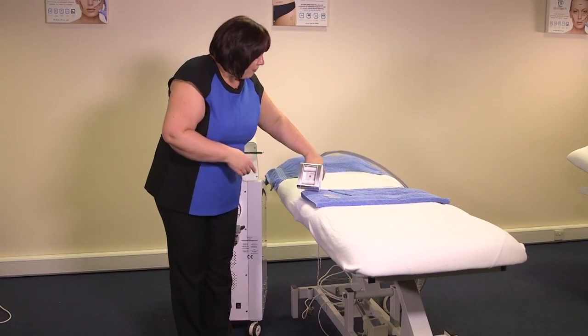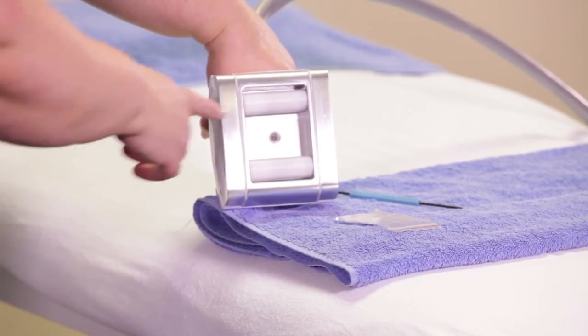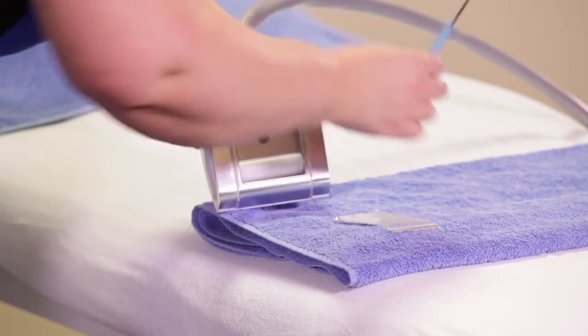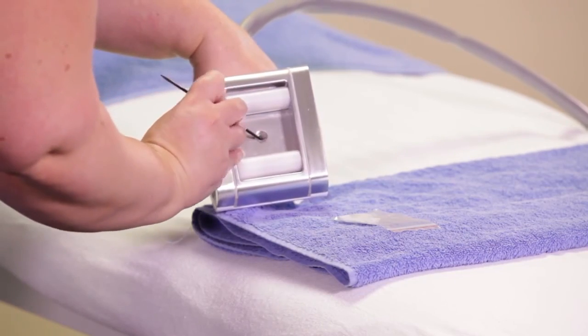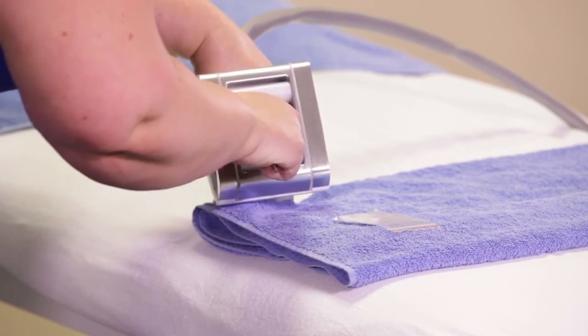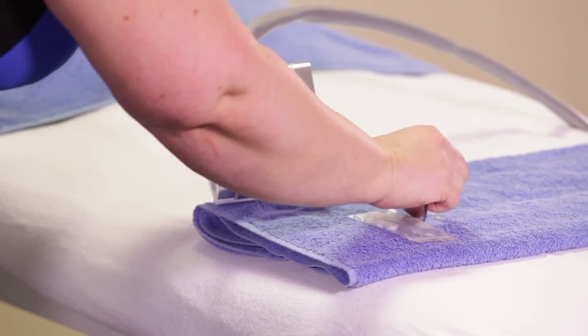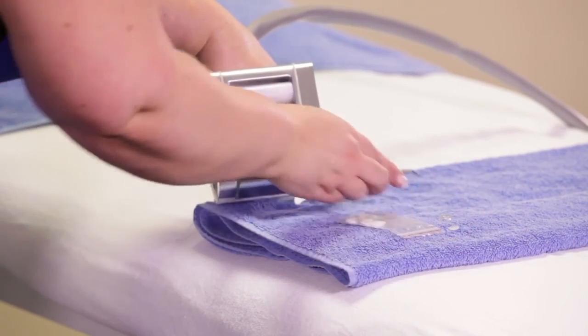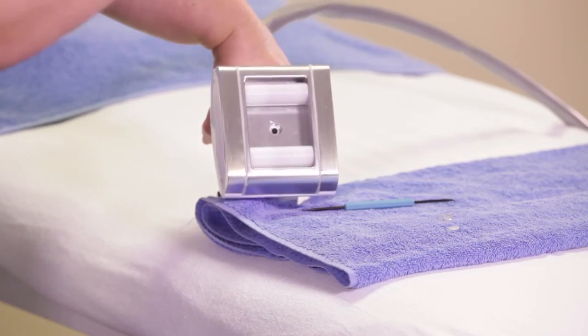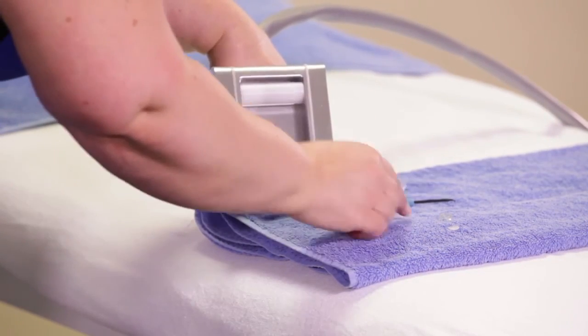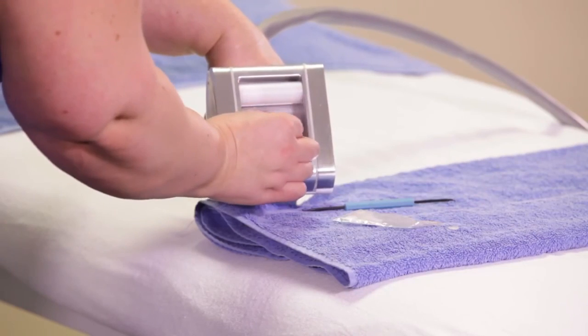In the Dermology RF, the other thing that we have to be careful of is the filter that's inside the handpiece. You'll have a hook with your system. There's a grommet which holds the filter in that you can take out with your hook. This filter will probably need to be changed after each Dermology RF client. You'll also be supplied with a bag of filters. The new filter then goes into the area and then you'll cover it over with the grommet to make sure it stays into place.